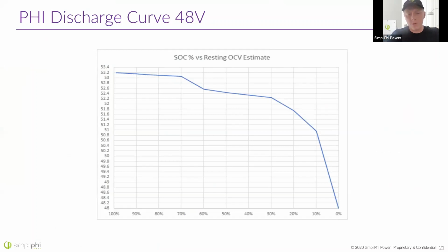What I'm wanting to demonstrate here is really just the discharge curve of our batteries. As you can see, it starts out quite high at 53.2. Now, as you're putting a load on that, you're going to notice the voltage really does not drop all that significantly until you get well below 52 volts here. So this is the 52 volt line, around 25% state of charge. And then finally, that voltage just begins to plummet.